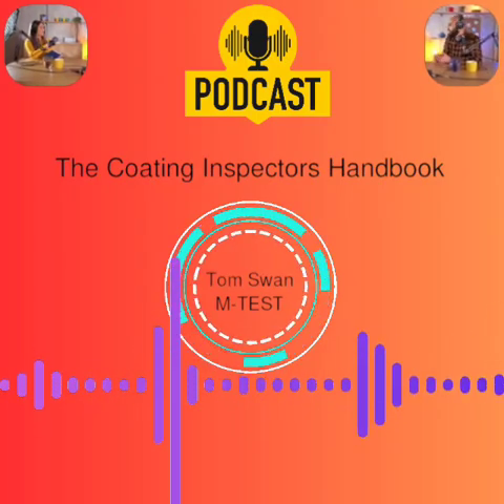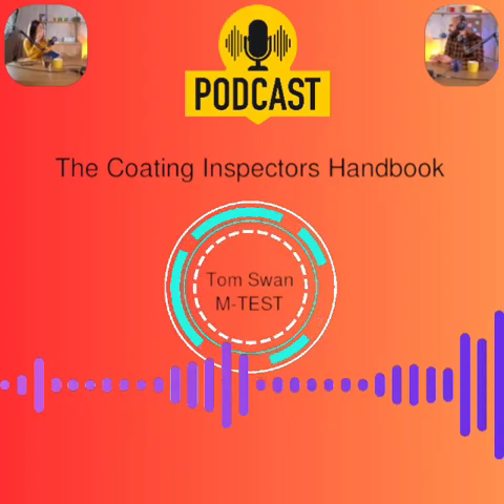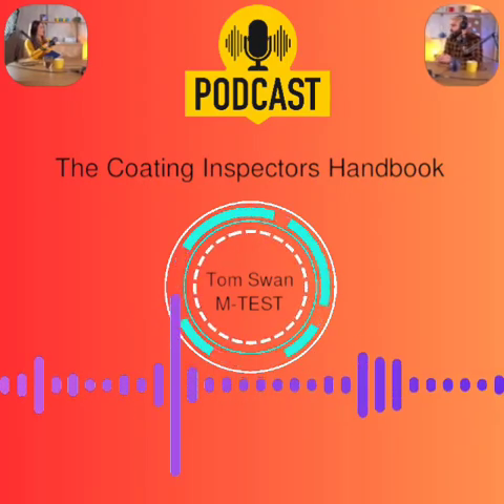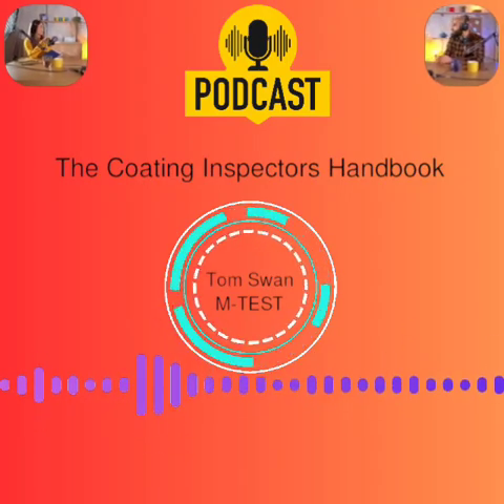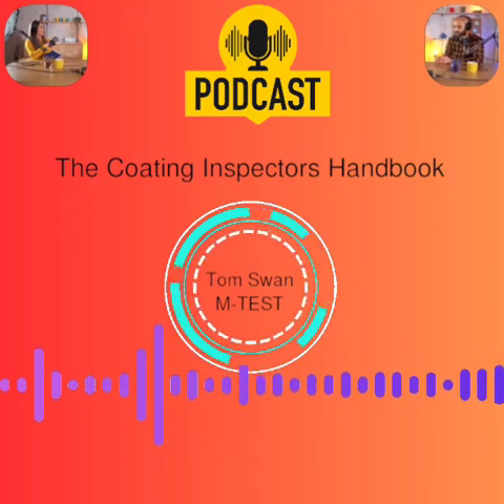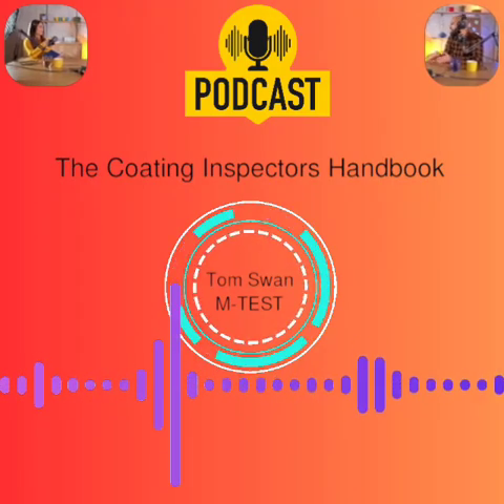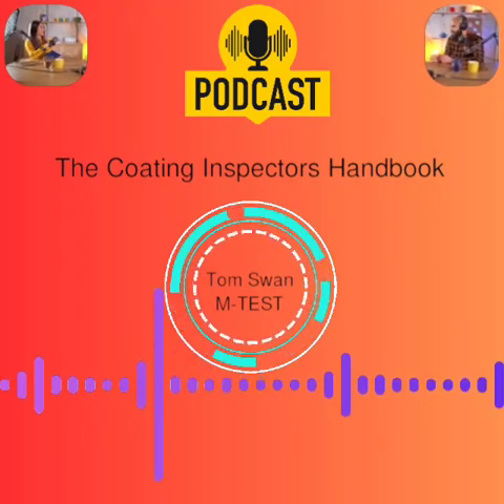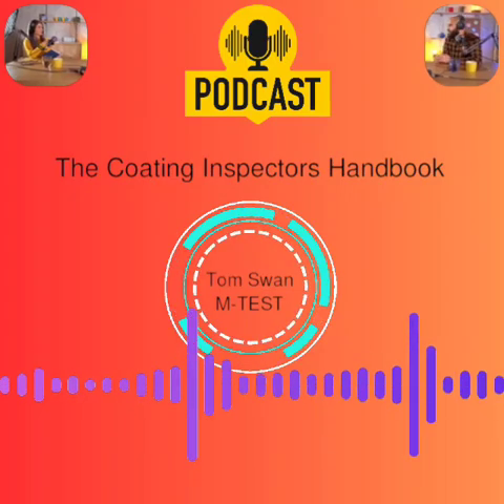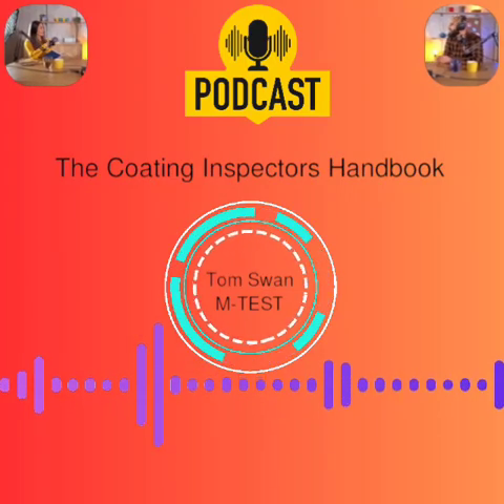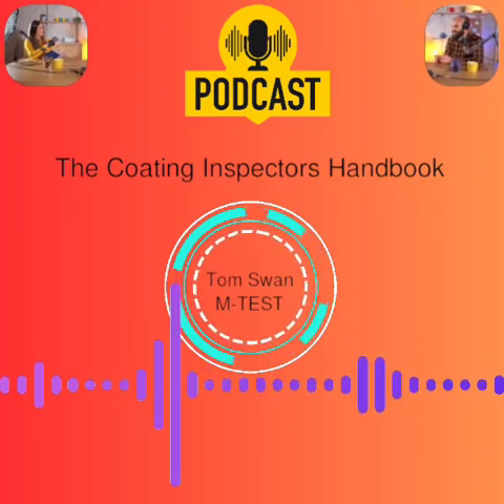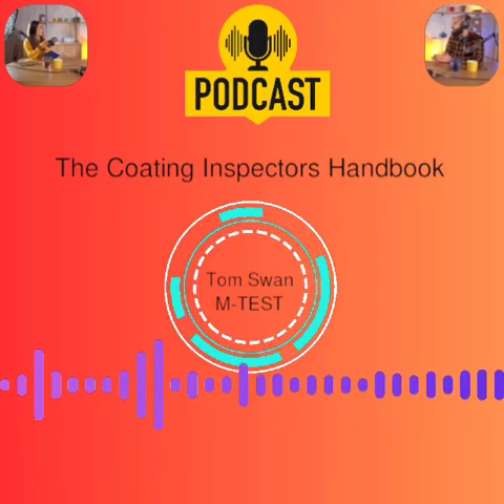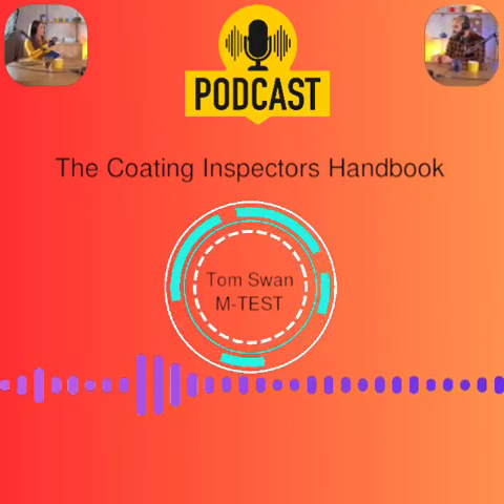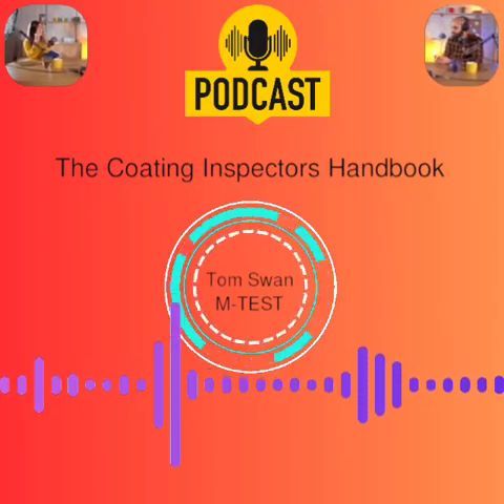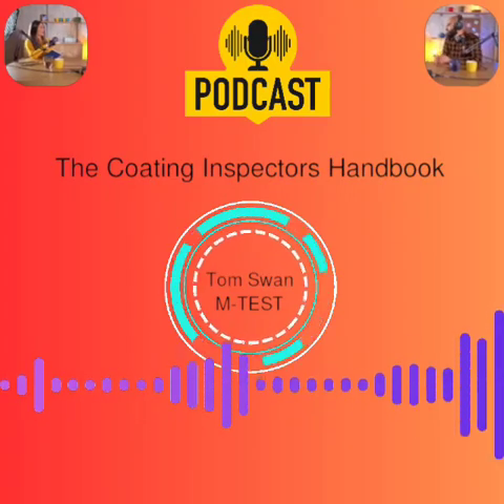Conforms to standards like ASTM D6132, ISO 2808, SSPC PA9. Limitation: coating can't have aggregate, usually. Thickness limits, polyurea, for example, absorbs the sound signal. Substrate evenness is huge. Concrete variations can be bigger than the coating thickness. What if readings are weird? Could be false echoes. Use high-low gates on the meter to filter signals outside the expected range. Take lots of readings, average them. Use couplant gel.